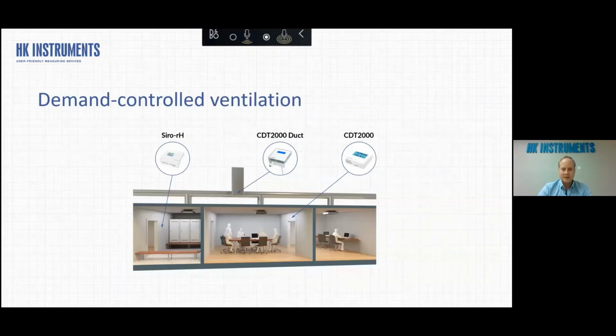And demand controlled ventilation is very popular nowadays. We are talking about these VAV systems, which can alter the flow rates based on occupancy level in different zones or rooms. So typically for demand controlled ventilation, we use CO2 as the variable to detect how many people there are inside the rooms or how bad or good the air is. So this is a very good strategy, this VAV system, for keeping an eye on the energy efficiency, because you don't need to over-ventilate the room, but just when the people are inside the room, you can raise up the flow rates to ensure a good and healthy atmosphere there.